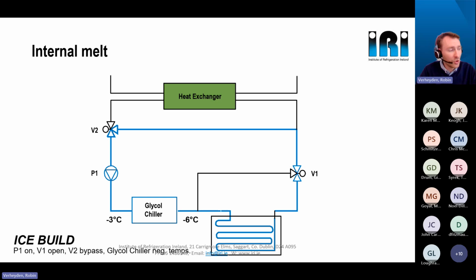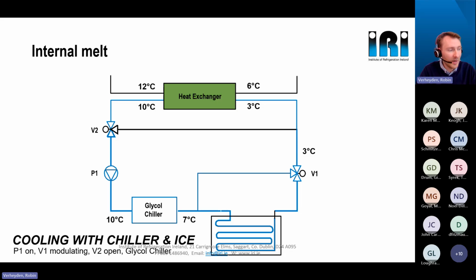In the next slide, we will show you how to melt the ice when the ice tank is needed. So, cooling with the ice and the chiller. We will use the chiller and ice tank in combination to have the most efficient solution. We keep the ice tank smaller by still using the chiller during the day. And we place the ice tank after the chiller, because the chiller then only needs to provide higher temperatures, while the ice tank will give lower temperatures because it's with ice. This gives a more efficient solution because the chiller is not forced to deliver low temperatures, but can work at higher temperatures and is more efficient.